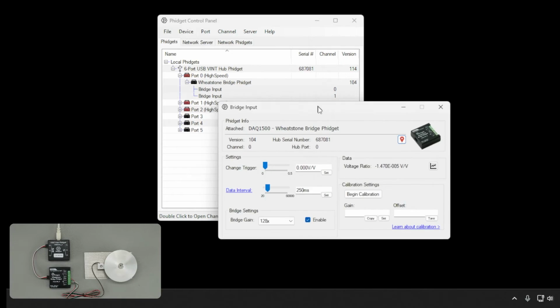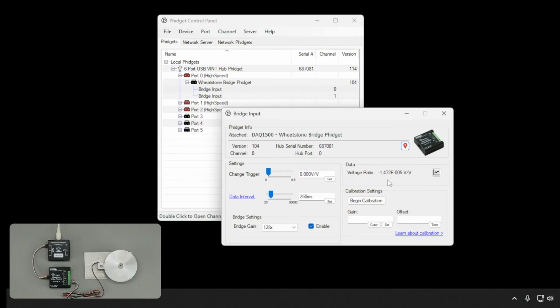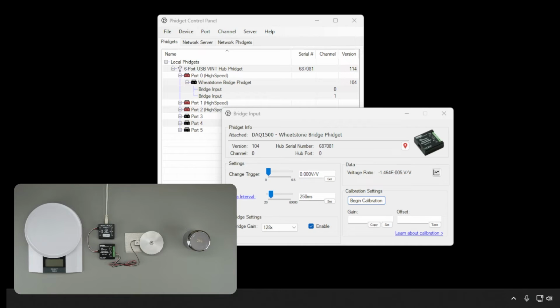We can view the output from our load cell using the Phidget control panel. The raw output is presented as a voltage ratio with units of volts per volt. Here, we can see the output of the load cell is about 14 microvolts per volt when the scale is unloaded. In order to convert this output to more meaningful units like grams or pounds, we need to calibrate our load cell. Calibrating is a simple process. You'll need a known weight, like this, or you can use a trusted scale to determine the weight of an everyday object. We'll calibrate through the control panel.